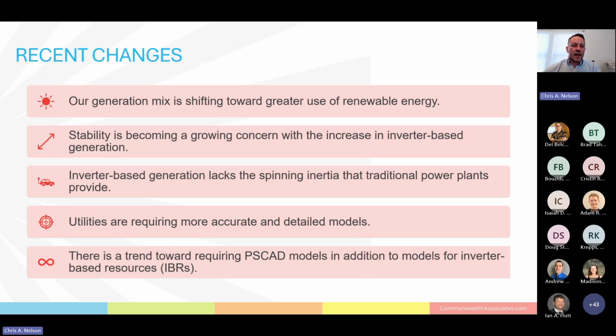I guess the biggest point we're trying to make here is that there's a major shift toward a lot more detailed modeling. Most of this is because of the shift toward renewable energy. There's a lot more smaller generators replacing all the larger generators we used to have, or those larger ones are still there, but they're not running because there's solar power running all day. Either way, there's not really any spinning mass, there's just not enough inertia behind the power that inverters provide.